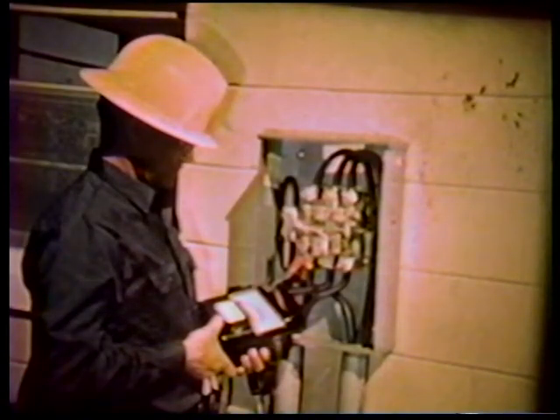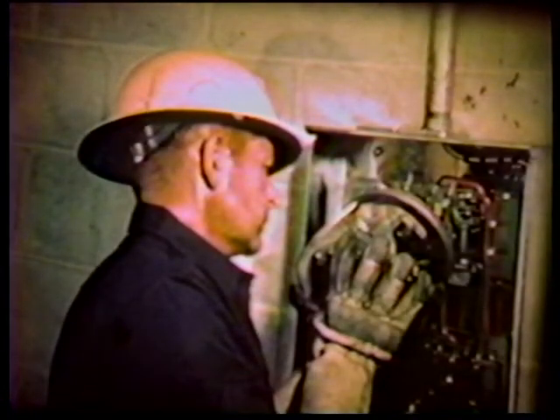Before a meter is installed in a new installation or where rework has been accomplished, a thorough voltage check of the socket should be made. This will prevent installing a meter on a ground, short, or feedback. These conditions caused by improper wiring will result in a dangerous flash. When inserting the meter into the socket, carefully line up the lower bayonets and socket jaws first.